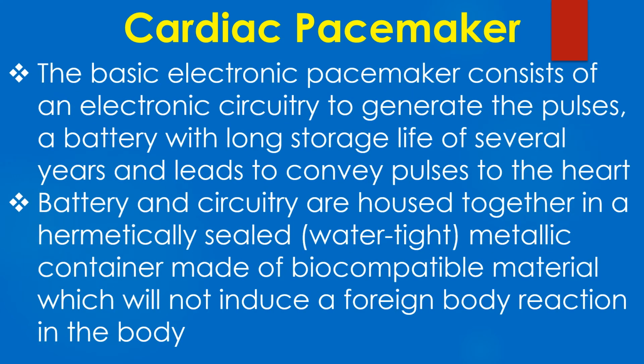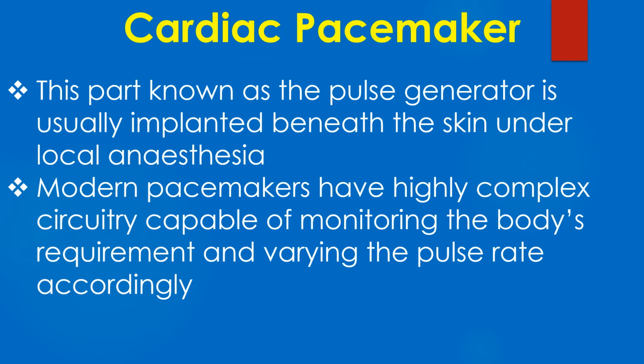The basic electronic pacemaker consists of an electronic circuitry to generate the pulses, a battery with long storage life of several years, and leads to convey pulses to the heart. Battery and circuitry are housed together in a hermetically sealed metallic container made of biocompatible material which will not induce a foreign body reaction in the body. This part, known as the pulse generator, is usually implanted beneath the skin under local anesthesia.